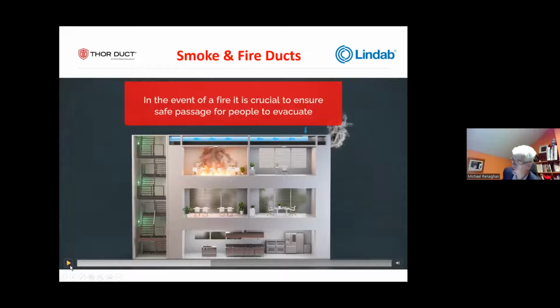The second application, which we're showing here, is what we call a pressurization duct. In the event of a fire, people are going to go to the escape routes and try and escape the building. In that event, specifically when it's very high-rise buildings, we need to provide a duct system that pumps fresh, tempered air from the outside into the stairwell so that smoke can't migrate to the escape routes.